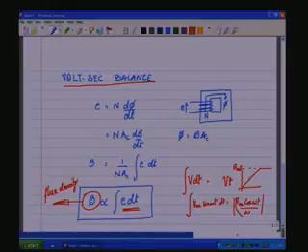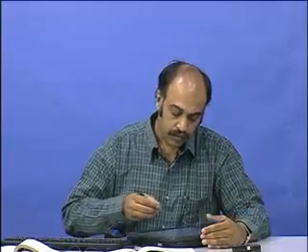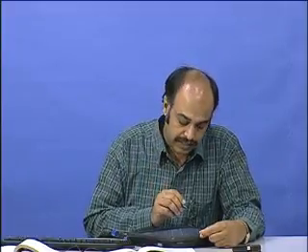The design value of Vm by omega should be such that this does not exceed B sat of the core. In such a case, the core will not saturate and it will retain its magnetic properties. This is the volt second balance which one needs to be conscious about while designing.